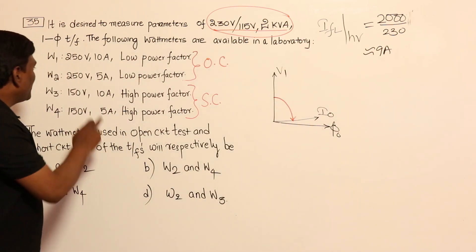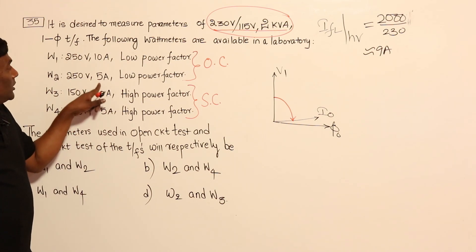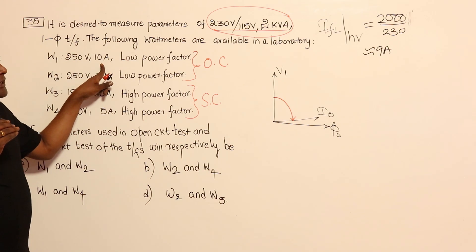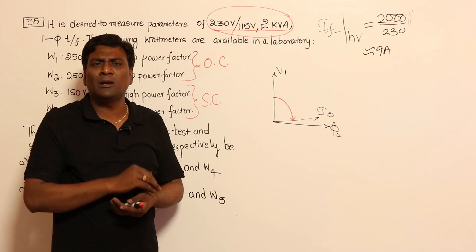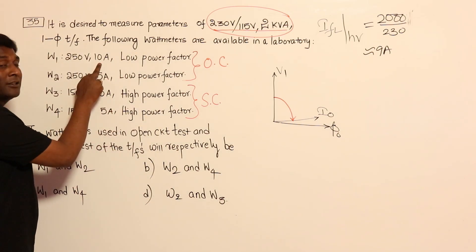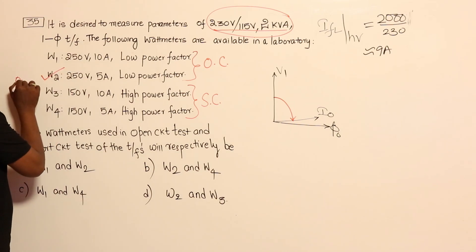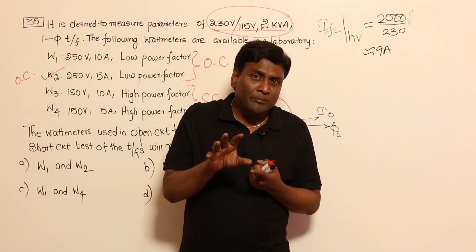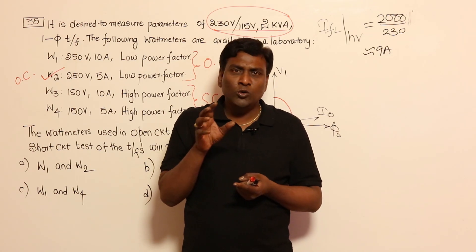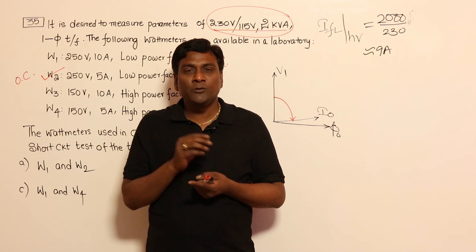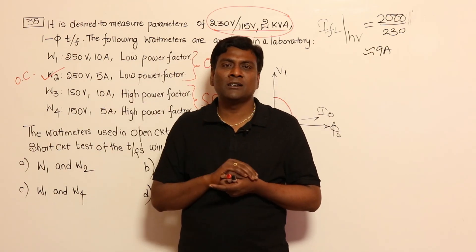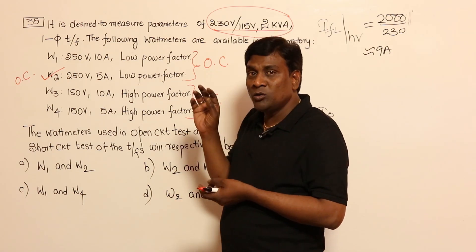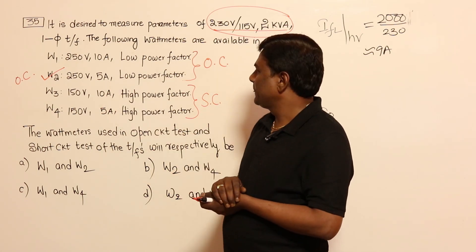On the HV side, full load current is 9 amperes. Should we select W1 or W2? W2, because full load current is roughly 9 amperes. But in the OC test, the no-load current is 2 to 10 percent of full load current — say 10 percent of 9 amperes gives roughly 0.9 or 1 ampere. Now, 1 ampere is nearer to the lower-range wattmeter. To measure 1 ampere, a 0–5 ampere meter gives less error than a 0–10 ampere meter. So we select the wattmeter with the 5A range, as 5A is nearer to 1A.